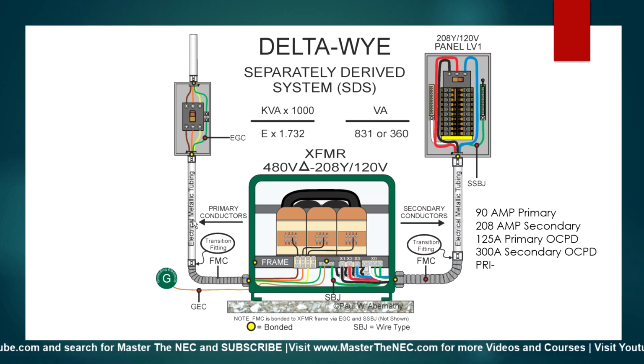Now, if this was EMT all the way to here, then that would qualify as an equipment grounding conductor, and I wouldn't have had to put the wire type in there. Okay, and it would have been already done. Now over here, same thing. This is FMC. It's not being used as an equipment grounding conductor.